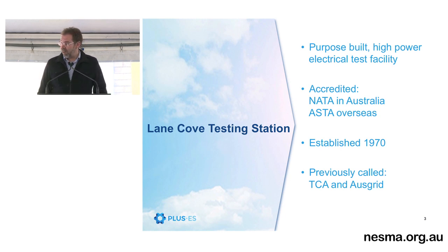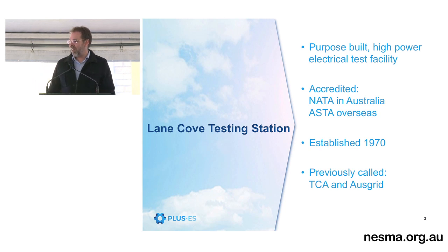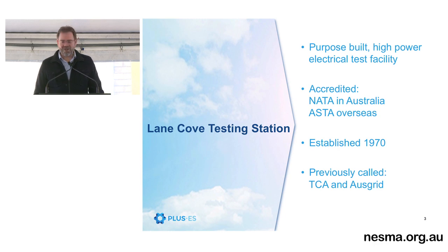Because of that 500 MVA fault level, it allows us to be in the club known as STL. STL is short circuit test liaison, and it's all the overseas test labs as well. They're like the Supreme Court or the High Court. If we have a disagreement about an interpretation of a standard, we can refer our decisions to the STL, and they update these guides. So the tests that we perform here at Lane Cove are consistent with the tests that are performed all around the world. Been around for a while, so next year is going to be our 50th anniversary.